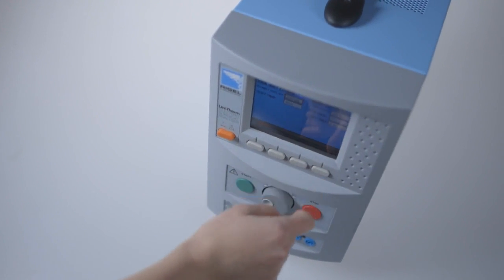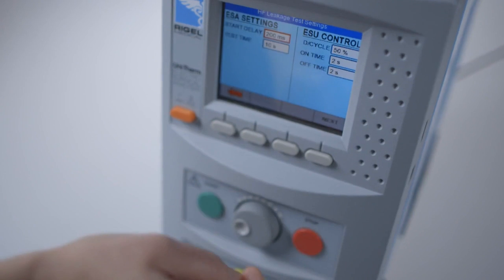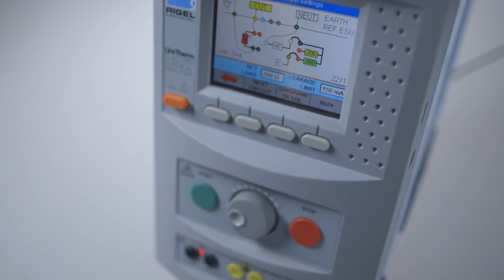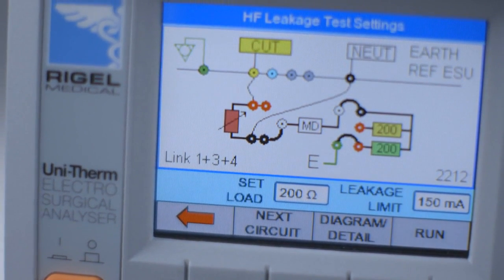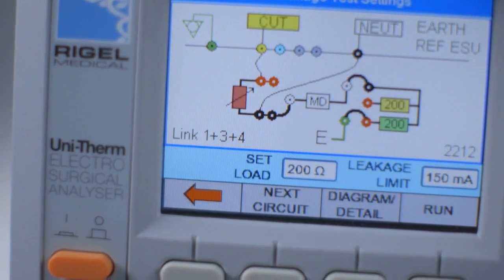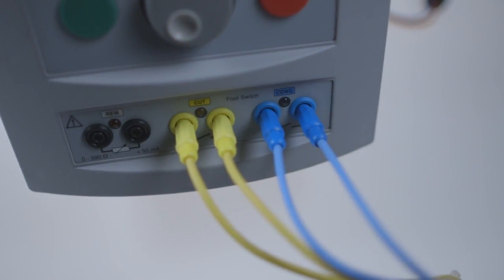This compact electrosurgical analyzer is packed with features aimed at reducing the time and complexity of testing electrosurgical generators. Detailed instructional diagrams on a color display simplify the complex test setup of high frequency leakage current measurements.